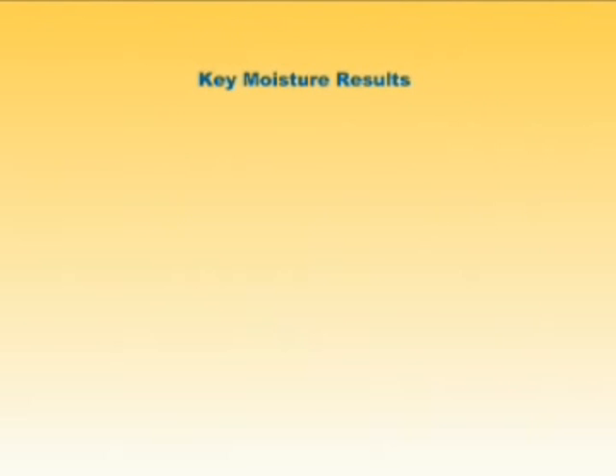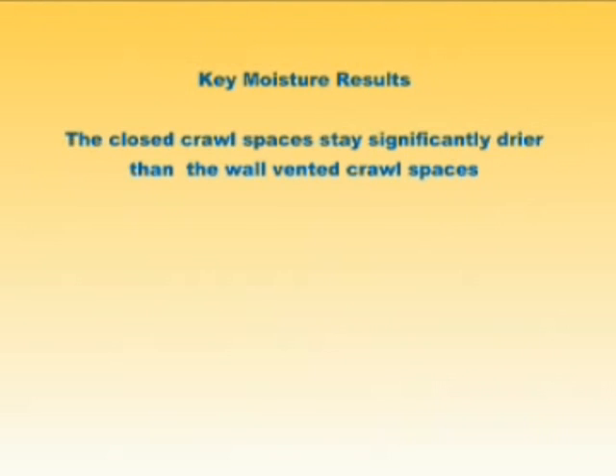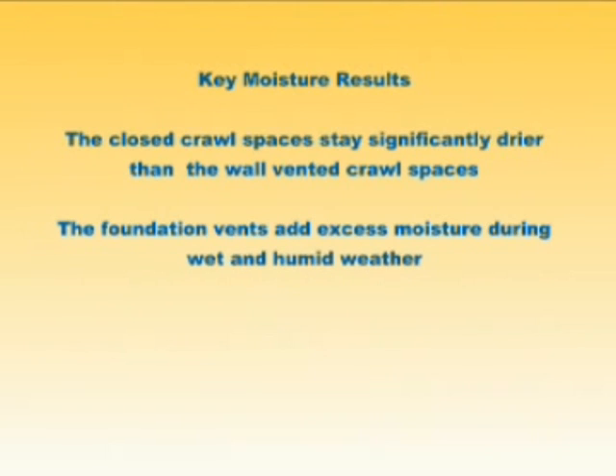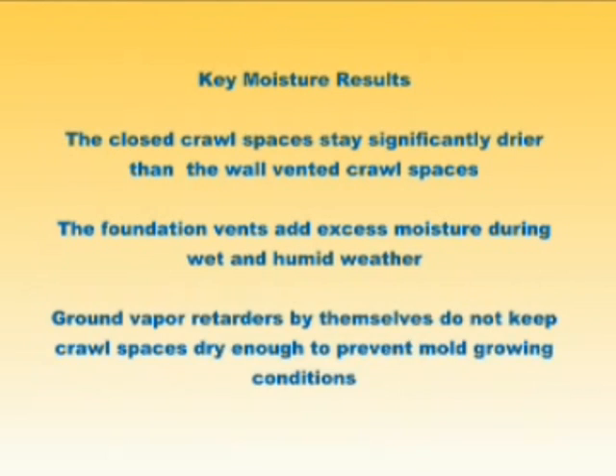The field test has operated for several years now, long enough that the moisture performance characteristics have become stable and predictable. The chief finding is that the closed crawlspaces stay significantly drier than the wall-vented crawlspaces. Second, the foundation vents add excess moisture to the crawlspaces during wet and humid weather, particularly in the summertime, and this excess moisture promotes mold-growing conditions. The last finding is that ground vapor barriers by themselves do not keep crawlspaces dry enough to prevent mold-growing conditions.